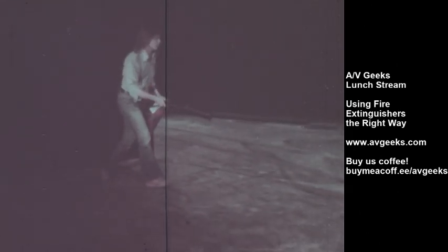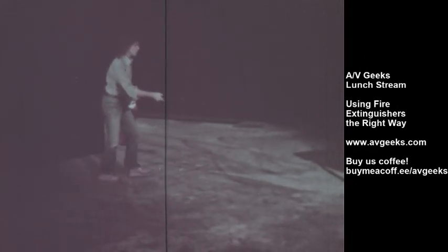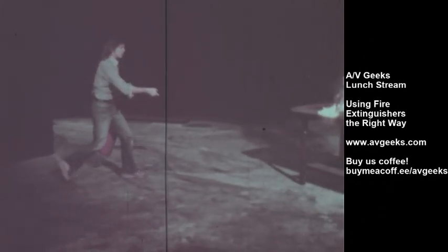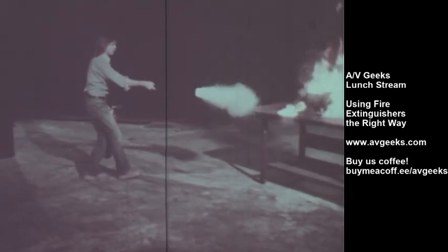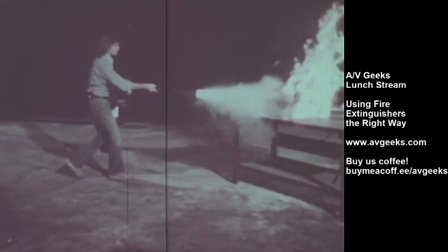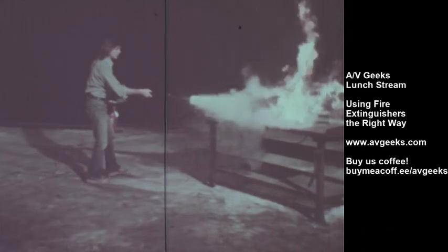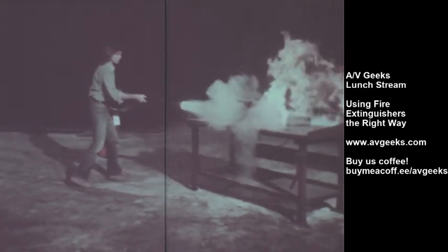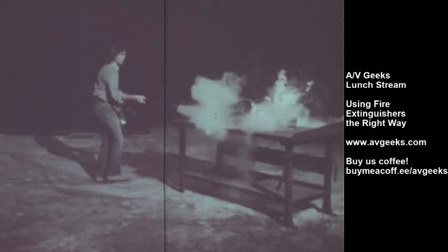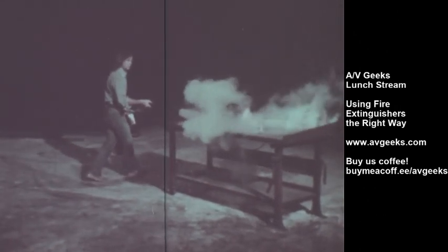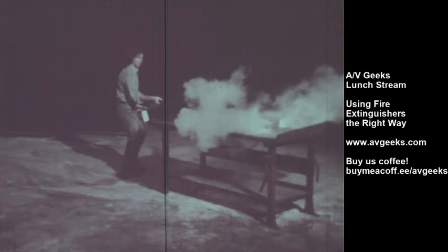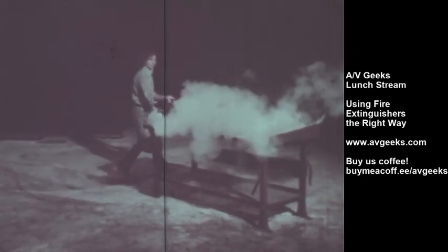To use a carbon dioxide extinguisher effectively, it is necessary to get even closer to the fire than you would with other types of extinguishers, 3 to 8 feet. This is because the carbon dioxide is released as a gas and readily dissipates. As with other extinguishers, the most effective technique is to sweep the extinguisher side to side, starting at the front edge of the fire and aiming at its base. The carbon dioxide blankets the fuel, restricting the free access of oxygen. In effect, it smothers the fire.